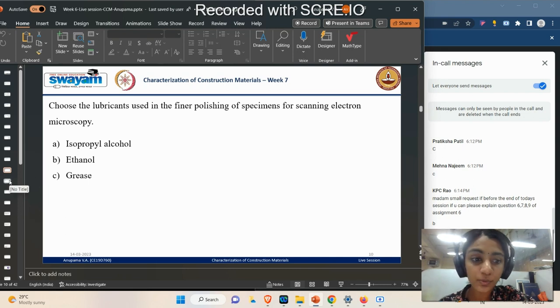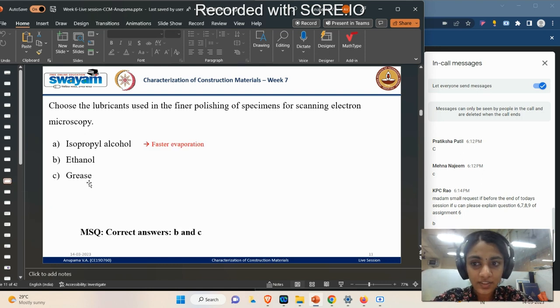Okay. So let's move to the correct answer for this question. The correct answers are B and C. Ethanol and grease are used as lubricants. Isopropyl alcohol we cannot use because of its faster evaporation rate. Okay, let's move to the next one.